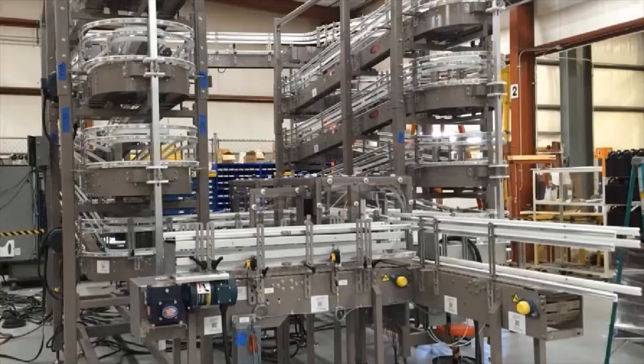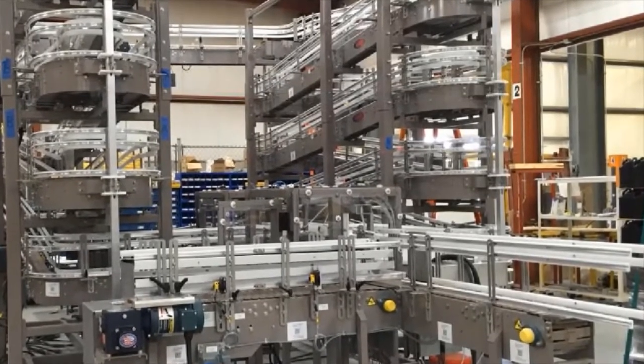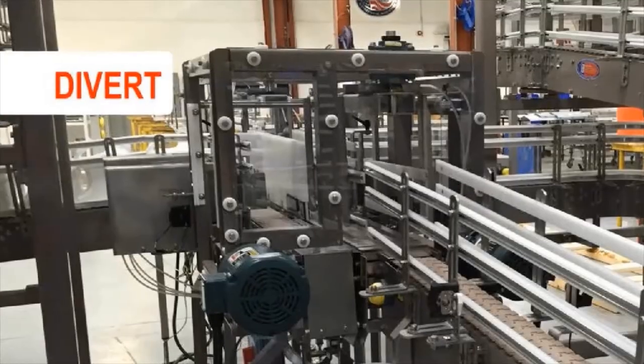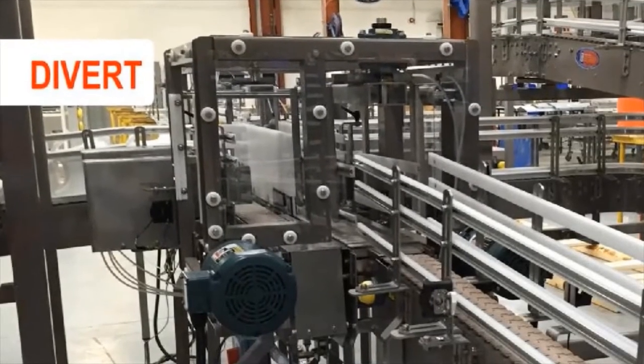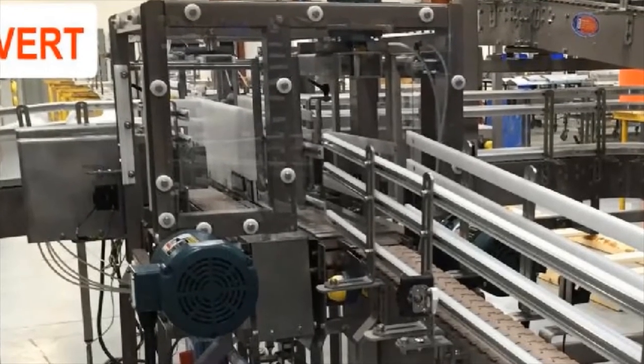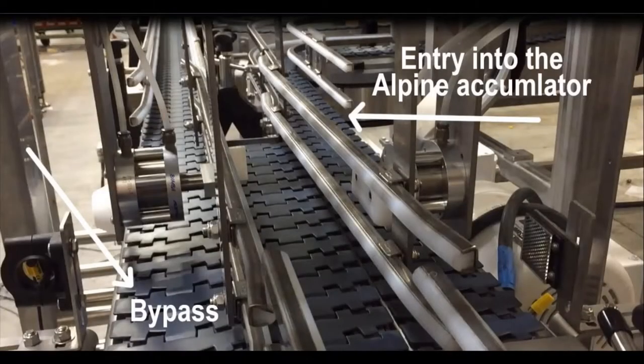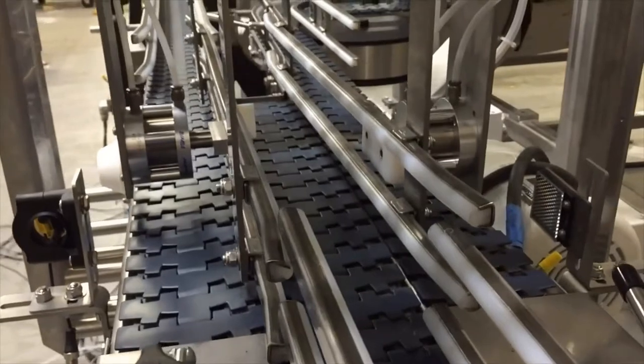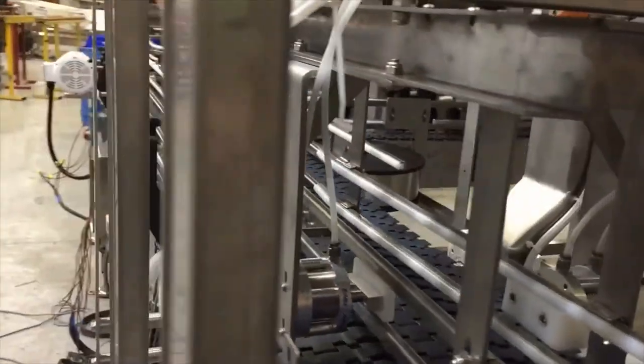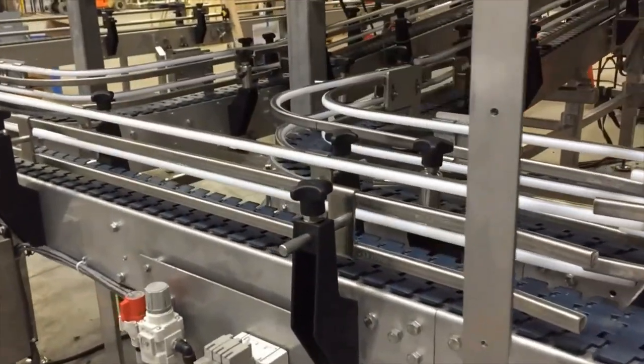Alpine systems deliver big results in a narrow footprint with simplified designs using standard conveyor components and controls. A pneumatic divert gate was incorporated to divert products onto the accumulation loop. Under normal conditions, the pneumatic divert will send 20% of the product onto the loop until the Alpine is at full capacity. The Alpine system is controlled by photo eyes, proximity switches, solenoids, and filter regulators. When triggered, pneumatic clamps will extend and divert product traffic directly into the vertical accumulator. Additional manual shutoffs were also installed.